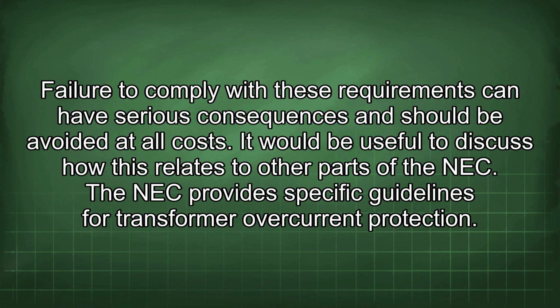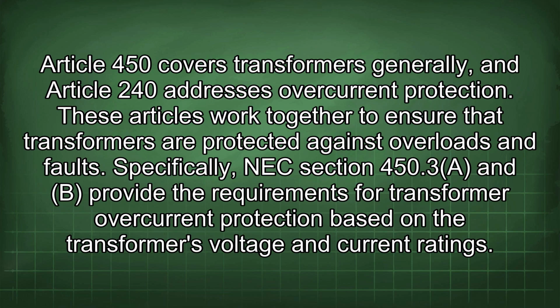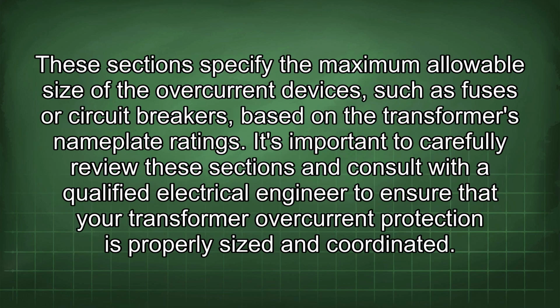It would be useful to discuss how this relates to other parts of the NEC. The NEC provides specific guidelines for transformer overcurrent protection. Article 450 covers transformers generally, and Article 240 addresses overcurrent protection. These articles work together to ensure that transformers are protected against overloads and faults. Specifically, NEC Section 450.3(A) and (B) provide the requirements for transformer overcurrent protection based on the transformer's voltage and current ratings. These sections specify the maximum allowable size of the overcurrent devices, such as fuses or circuit breakers, based on the transformer's nameplate ratings. It's important to carefully review these sections and consult with a qualified electrical engineer to ensure that your transformer overcurrent protection is properly sized and coordinated.